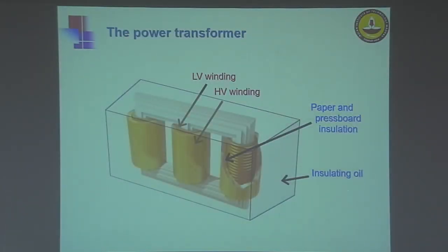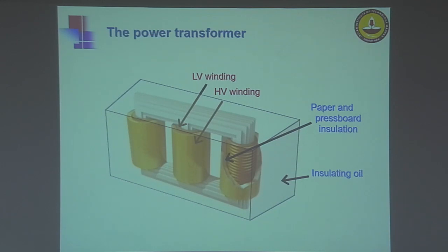Let us move into the structure of a power transformer. Here I have a three-phase transformer which has three sets of primary low-voltage windings and secondary high-voltage windings wound around a core. Each of these windings consists of multiple layers of conductors which are paper-insulated, and the windings are insulated with a press-board layer in between. In an oil-filled transformer, the entire structure is immersed in insulating oil, which also serves the dual purpose of acting as a coolant.